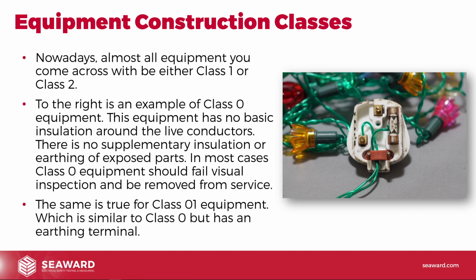It is allowed in very specific testing environments, maybe where you've got an insulated environment, a rubber room, for example. But for normal PAT testing, in a normal place of work, if we see class 0 or class 01 equipment, generally that's failed on site. So we only mention it here really. It is very rare, but you may come across the odd piece of older equipment and wonder what's going on with that. But as I've said in the slides, most of the equipment you'll come across will be either class 1 or class 2.